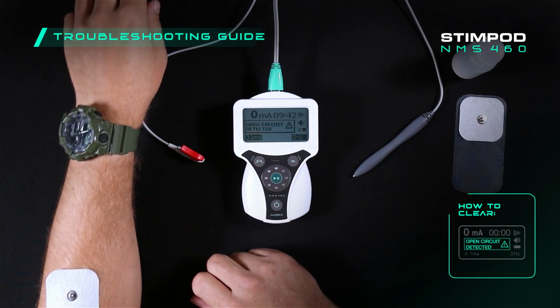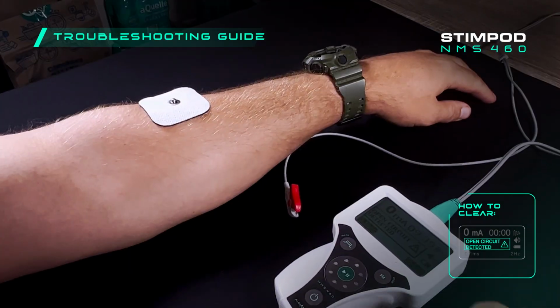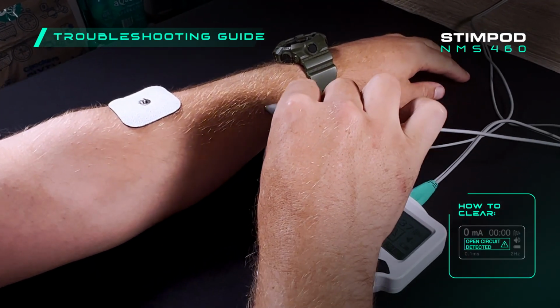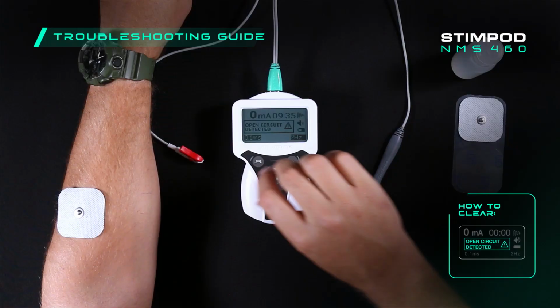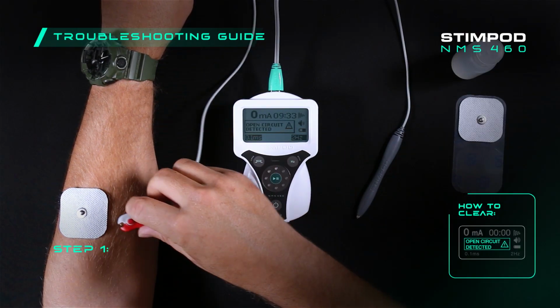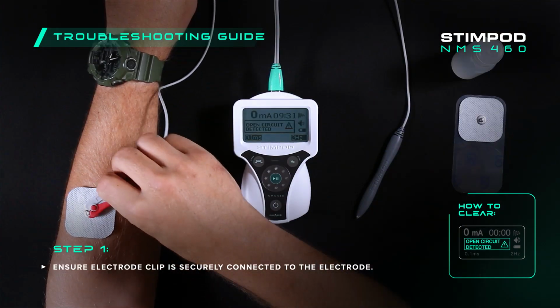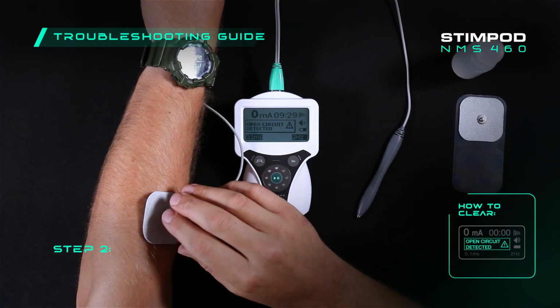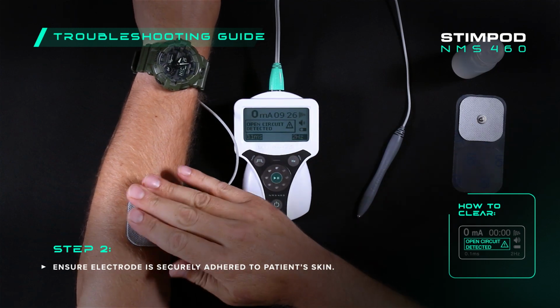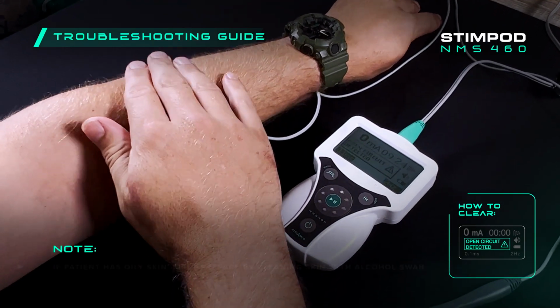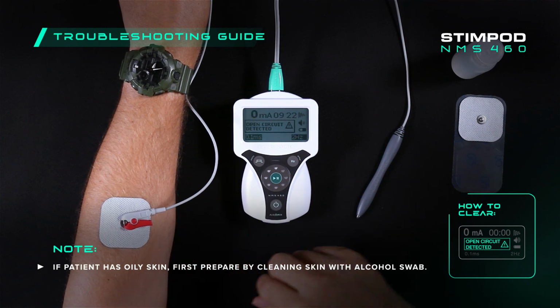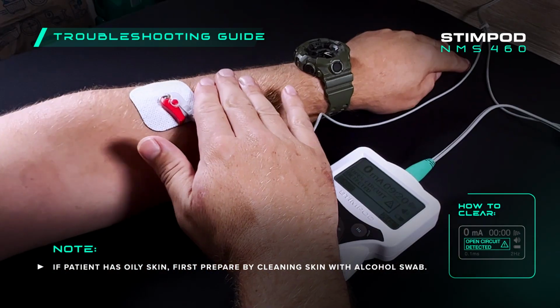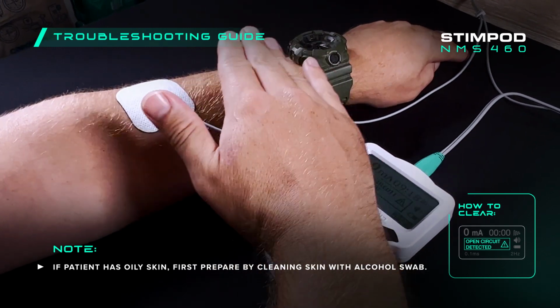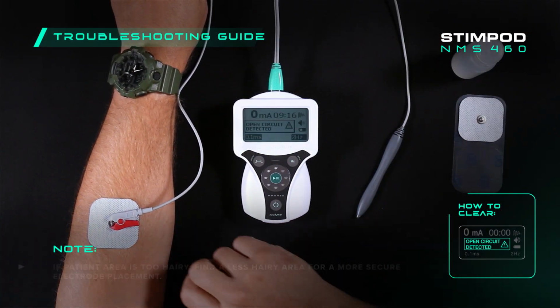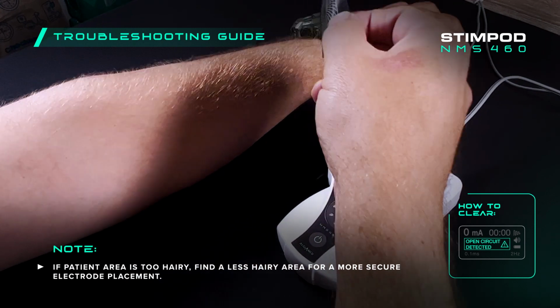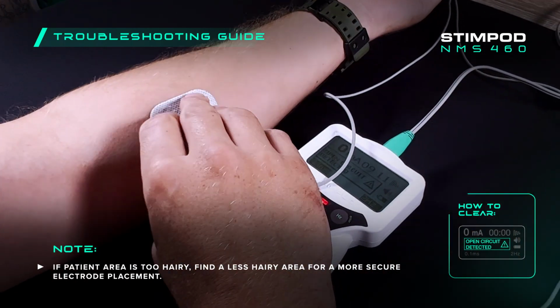If the open circuit detected message is still displayed when touching the skin surface with the treatment probe, ensure you have done all of the following correct preparations. 1. Ensure the electrode clip is securely connected to the electrode. 2. Ensure the electrode is securely adhered to the skin surface. Some skin may be too oily, which will prevent the electrode from sticking adequately. With oily skin, it's always better to first clean the area with an alcohol swab. If the area is too hairy, it's best to find an alternative area on the body to place the electrode.